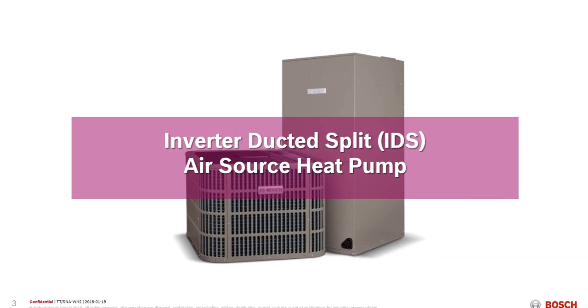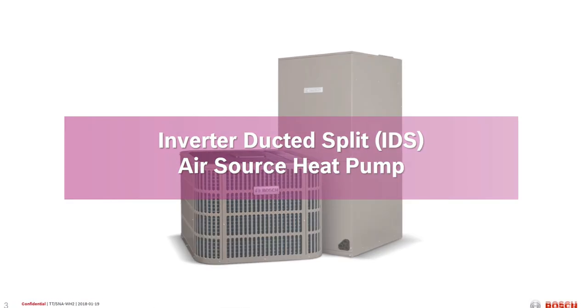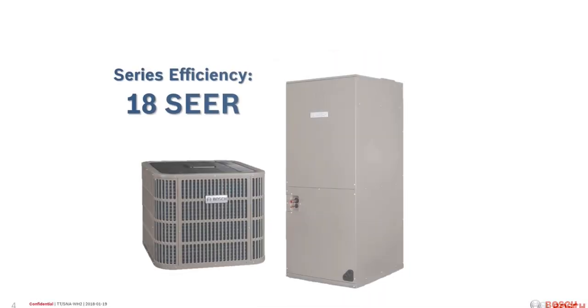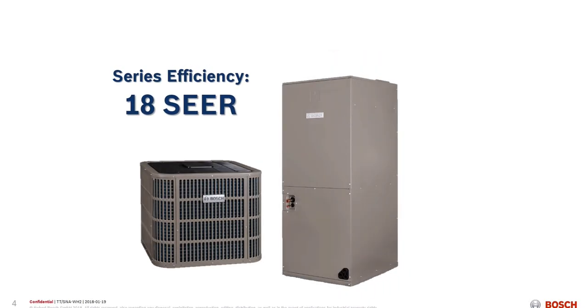Today we're going to talk about the IDS, what we would call the inverter ducted system. Kind of like a mini split, air source heat pump, but yet we now have ductwork matched up to an air drive machine, whether it's a gas-fired furnace or, in this case, an electric air handler. We've got an 18 SEER air source heat pump. There's my condensing unit and the one-piece air handler.